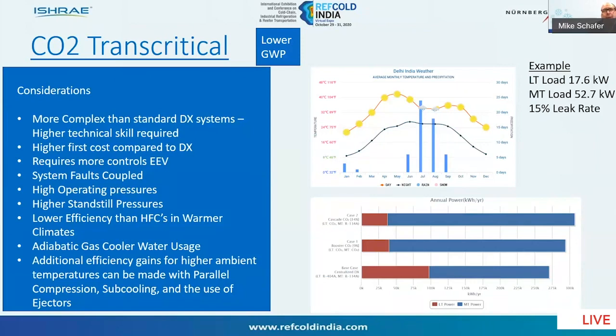The other thing to note, of course, that we talked a bit about, is that CO2 transcritical has a lower efficiency in the warmer climates because it's operating predominantly in a transcritical mode. The other consideration is the amount of water that's required for the system if you're using an adiabatic gas cooler. And then there's been a lot of gains over the standard booster system, by parallel compression, ejectors, and subcooling.